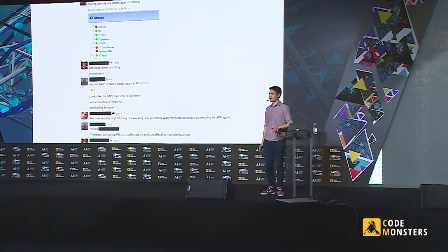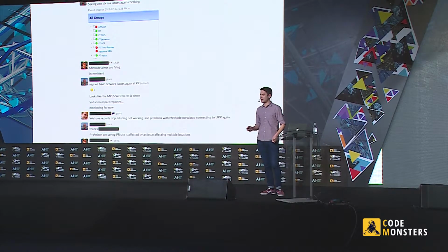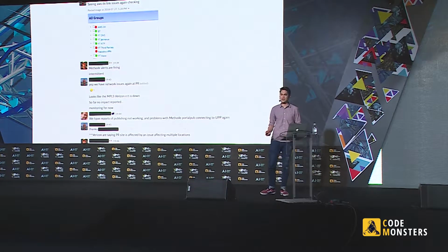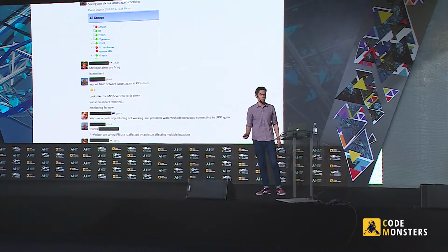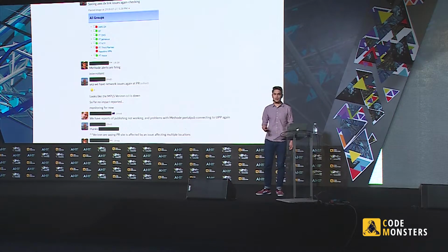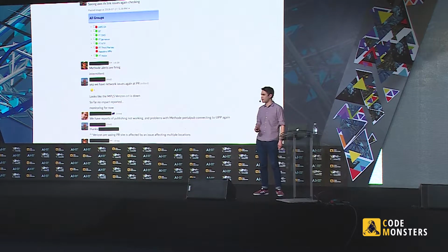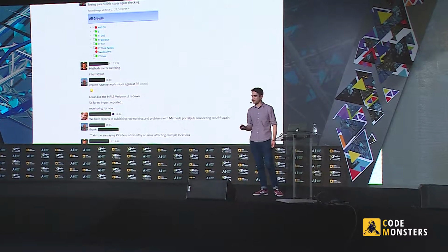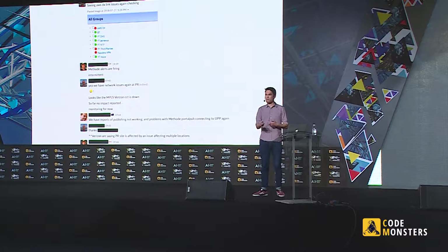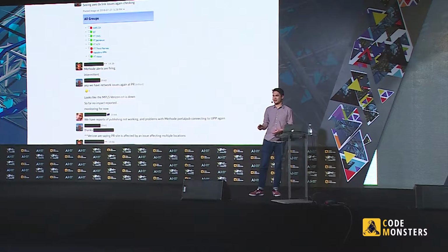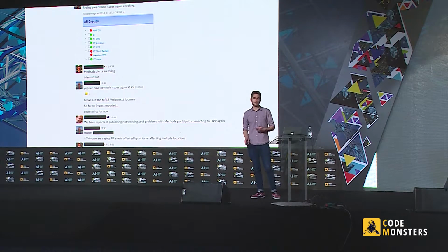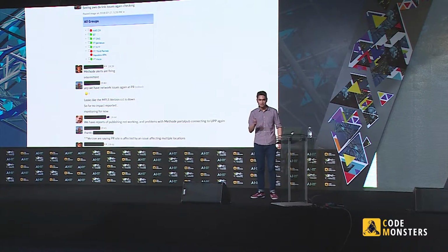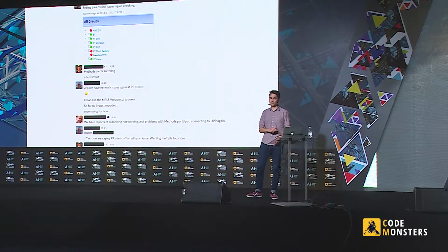Later on, we found that the cause of the problems was actually another customer in this data centre, decommissioning some of their network equipment. And in the process of doing that, they cut the fibre connection that provided internet to 90% of our servers. There's probably not many ways that we could have predicted that happening at that time. And it did take us roughly 5 days for network connectivity to be fully restored, and for all of our services to be back to high availability and running out of both data centres again.